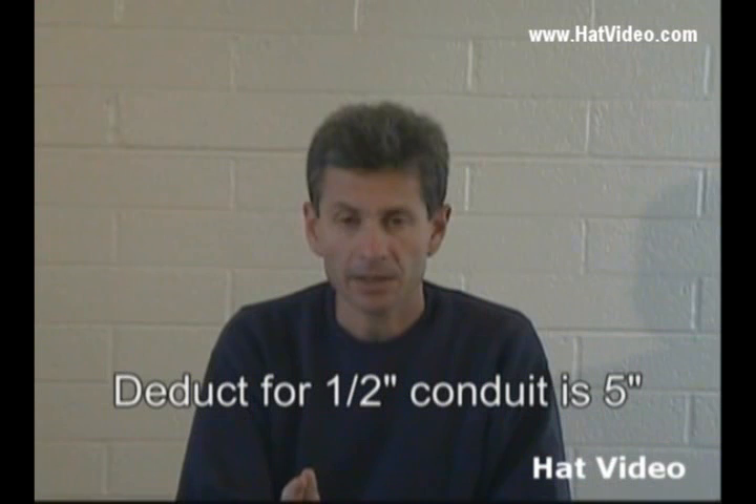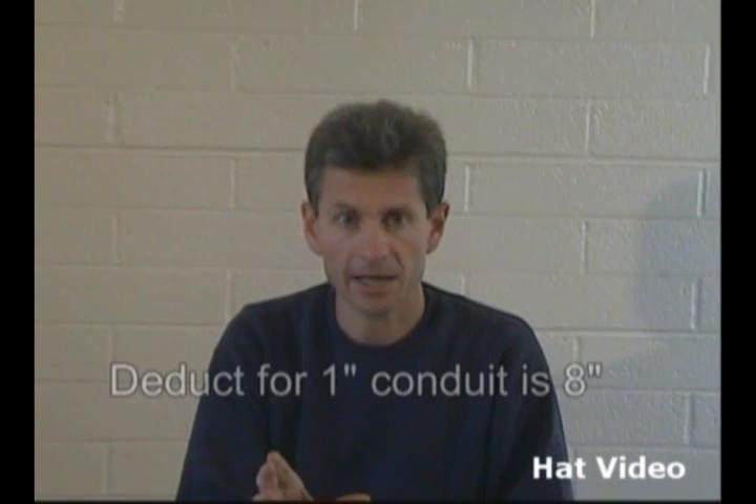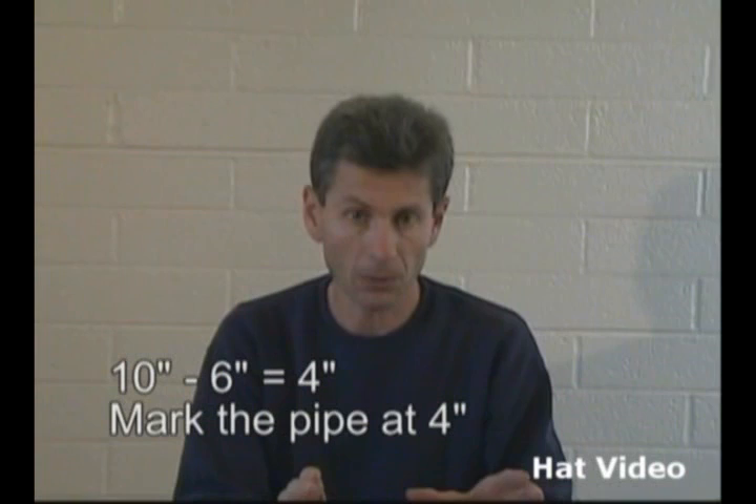Let's talk a little bit more about deducts. On half-inch conduit, the deduct on a 90-degree angle is 5 inches. On three-quarter-inch conduit, like what we just bent, it is 6 inches. On one-inch conduit, the deduct for a 90-degree angle is 8 inches, and we subtract that from 10 and get 4. So we mark our pipe at 4 inches, place the arrow mark on 4, make our bend, and our 90 would end up being 10 inches long. So let's do that.